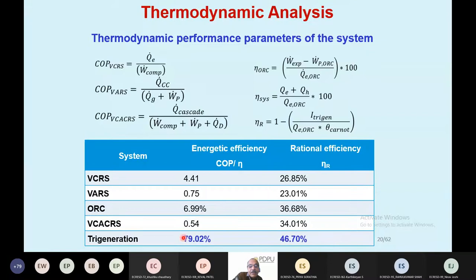Whatever energy is used, we are utilizing it in a very good way, and therefore exergy losses are reduced. That's why around 46.7% second law efficiency is achieved. The second law analysis shows where irreversibility losses occur in each component, and based on that the designer can decide which component is more sensitive and which is less sensitive. That is the main gain from this analysis — the results are very important. Tri-generation systems can achieve close to 80% efficiency, whereas individual subsystems have much lower efficiencies.